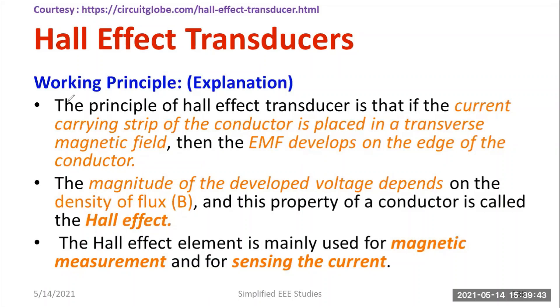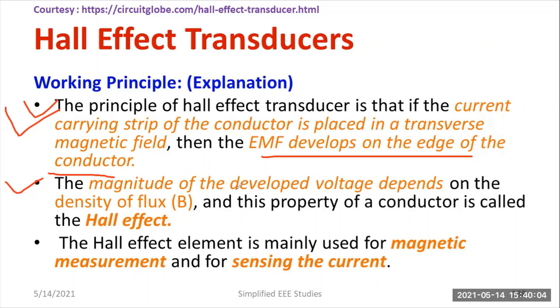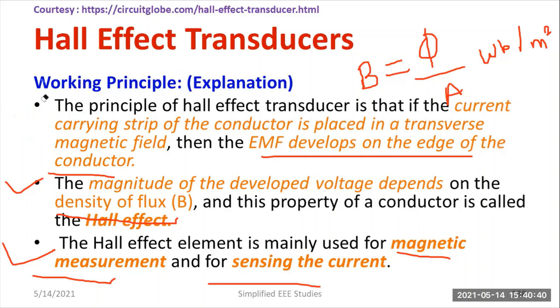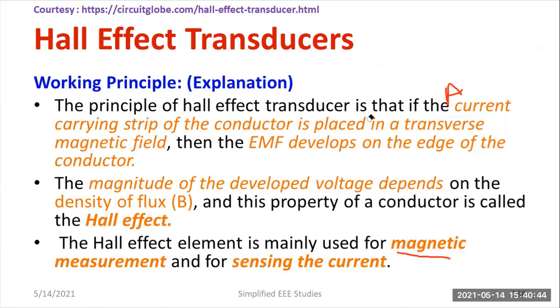The principle of the Hall effect transducer is that if a current-carrying strip of conductor is placed in a transverse magnetic field — meaning both are perpendicular — then an EMF develops on the edge of the conductor. The magnitude of the developed voltage depends on the flux density (flux per unit area, expressed in Weber per meter square). This property of the conductor is called the Hall effect, and the Hall effect element is mainly used for magnetic measurement and sensing current.